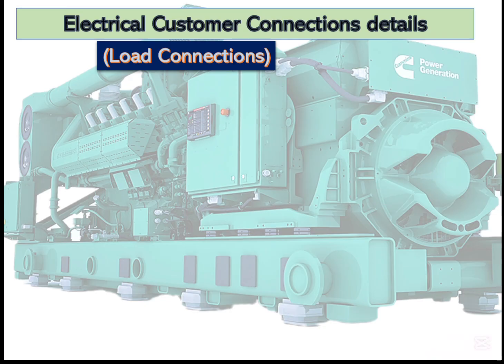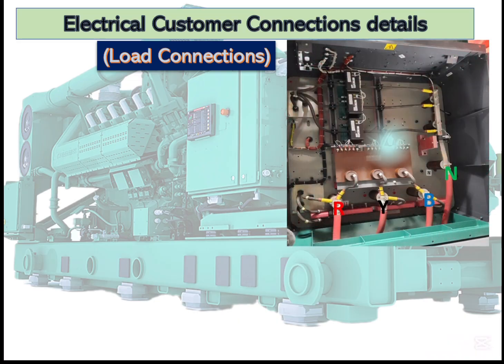For the electrical installation, the first connections are the load connections, where we connect cables to our load tank. So let's look at where we can collect our load connection. The load connections are always collected from the alternator terminal. So this is an overview of the alternator when we remove the top cover. Here we mentioned red, yellow, blue and neutral. The transformer and the alternator are mostly wound in star connection. So this alternator supplied is also a star connected winding. So we have red, yellow, blue and neutral from here.